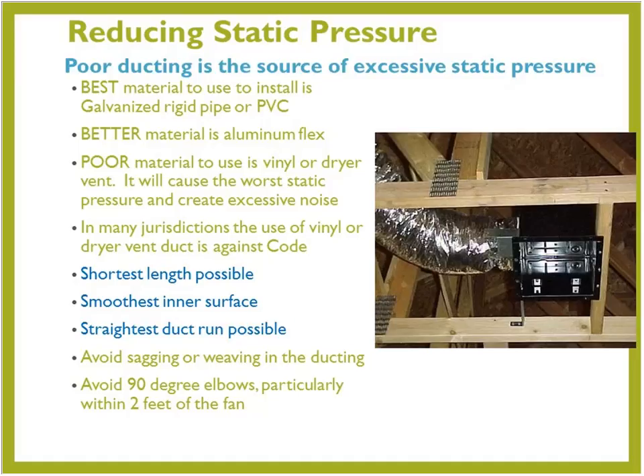Even if you're using flex duct, I think the manufacturers recommend that you stretch that flex duct to 5 pounds of pressure so that it smooths out the inside of that flex duct and reduces the static pressure, so you don't get cavitation when that fan is pushing air through that duct. So again, if you keep it short, smooth, and straight, and then put a good termination on the end of it that doesn't have a lot of resistance, you're going to certainly improve the performance of the equipment.